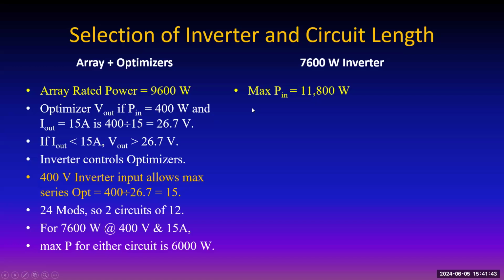I'm sorry, this is not, oh, the maximum input power is 11,800 watts. That's DC. That's not the output power. You can have an 11,800 watt array. The DC to AC ratio is still acceptable. And the reason is because the actual power in is almost never going to go very much over 7,600 watts, less than 1% of the time. And on that time, the inverter simply does current limiting. All right, maximum input voltage 480.